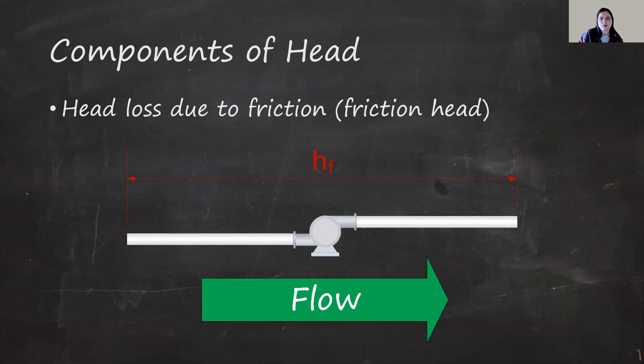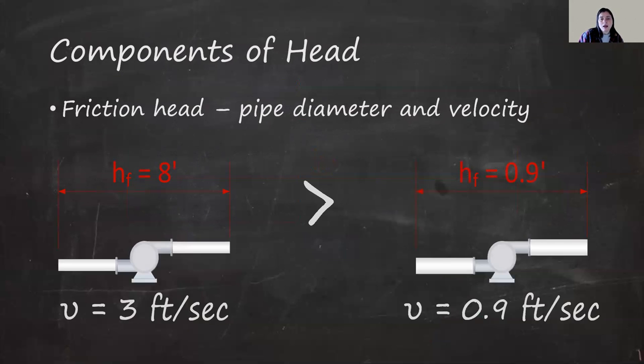Friction head is the amount of energy lost due to friction forces when traveling from the source to the destination. The head required to overcome the friction in the pipe depends on the velocity of fluid, which is dependent on the diameter, length, smoothness of the pipes, and the number of fittings. The value is typically calculated using the Darcy-Weisbach equation, along with the friction factor and Reynolds number. I recommend a nice Excel spreadsheet or a web app that allows you to calculate this easily based on different pipe diameters, flow rates, and distances.